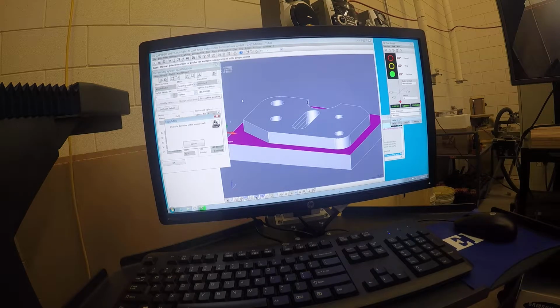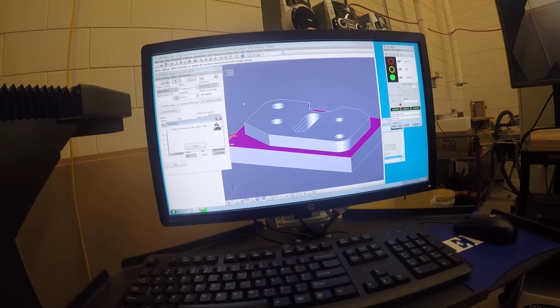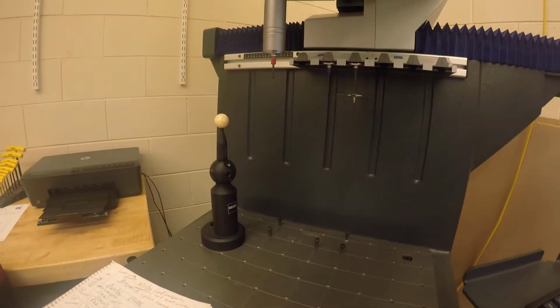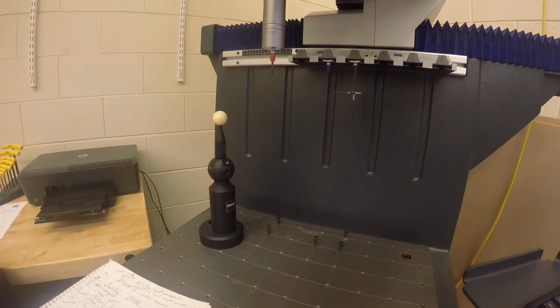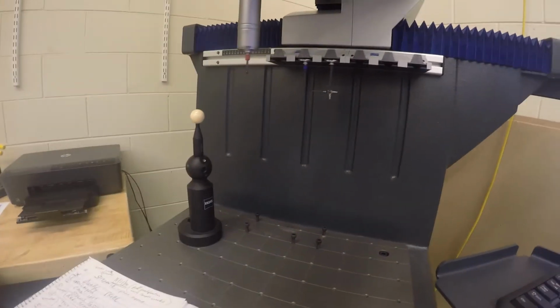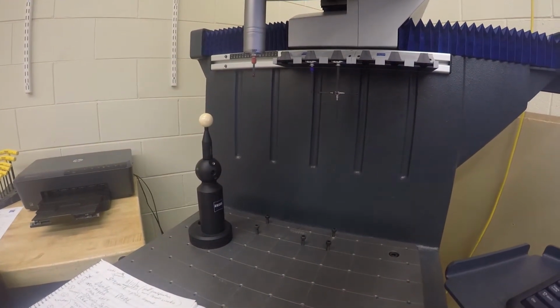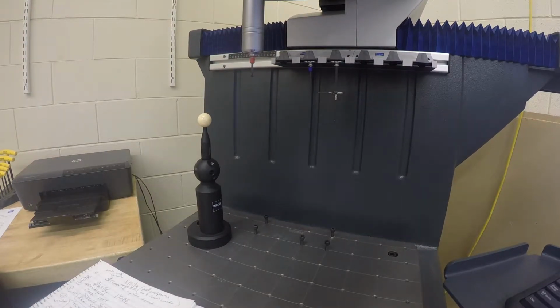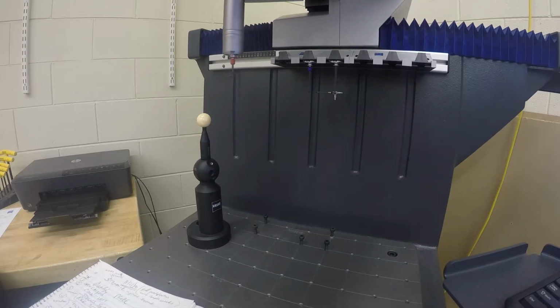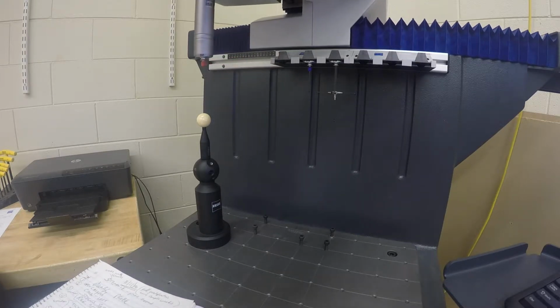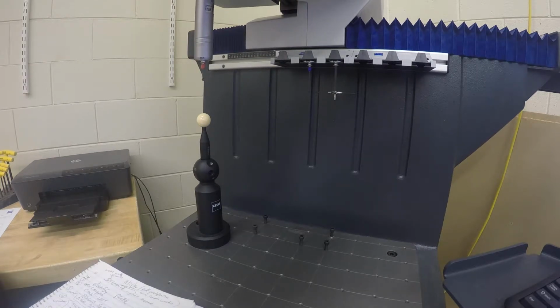So we need to go over to the top of the reference sphere, over the center of it, and jog down until we touch. And then it will take over. Unlock my axis, turn up my feed. So it has a little sub-program that it's going to run. Try and get as close as I can to the center. Looks pretty close.